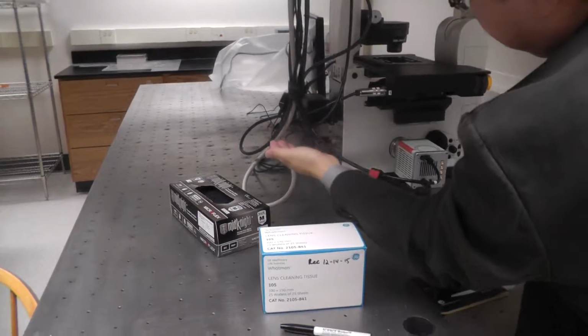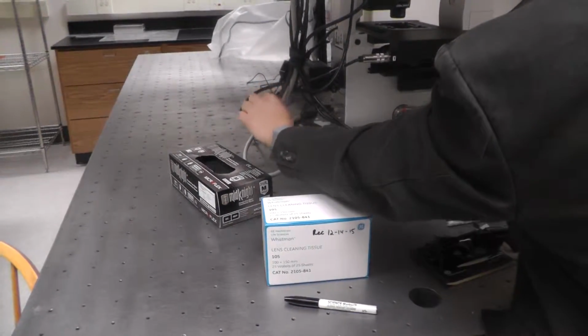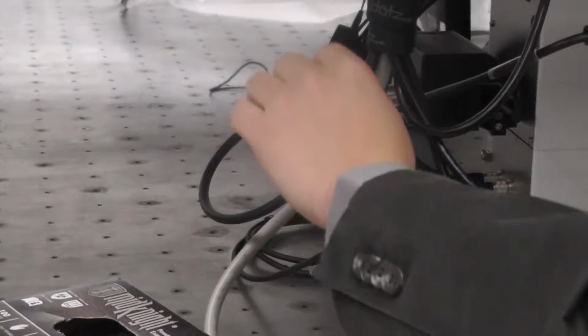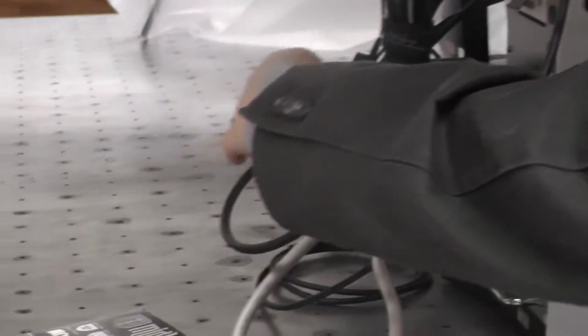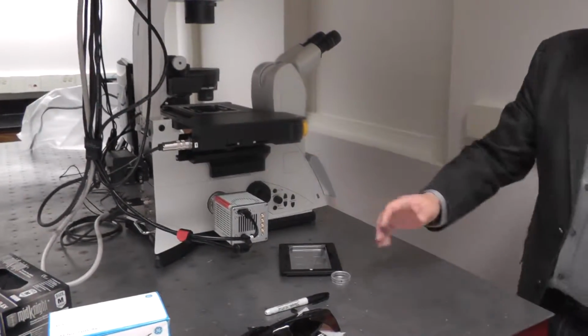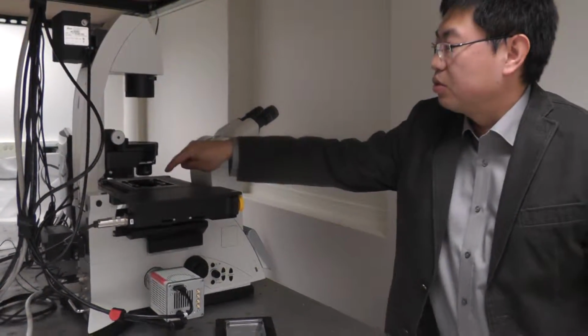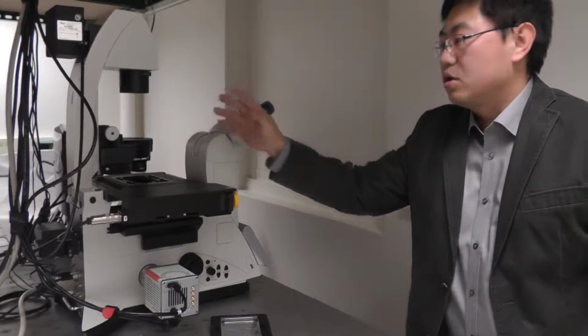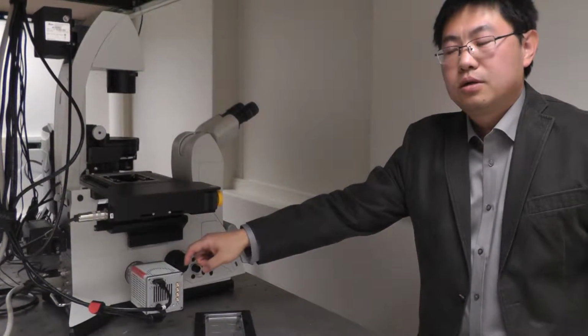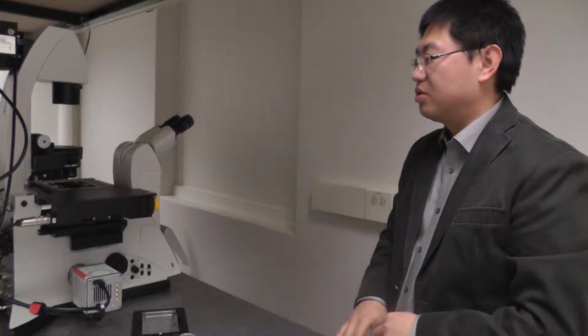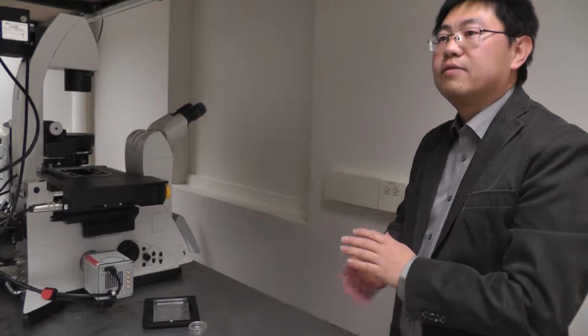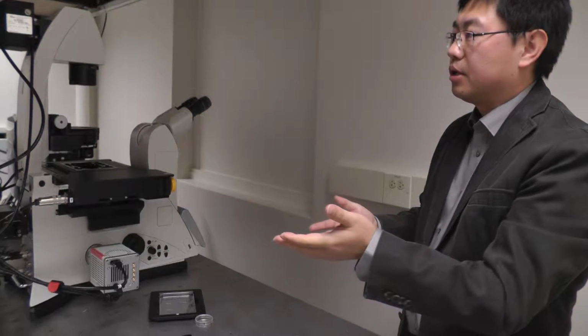See all these wires, including this, the so-called light guide. The light from the LED is transported within this guide and then put into the microscope. The light also comes from the back port of the microscope. Within the microscope, there's also a filter set to reflect the light up to the objective, and the objective will collect the fluorescence and direct it to the camera. This one is more like a toy. You can just press a button, move, and record the image. It's easy to use, but the sensitivity is not as high. That's why we have both microscopes.